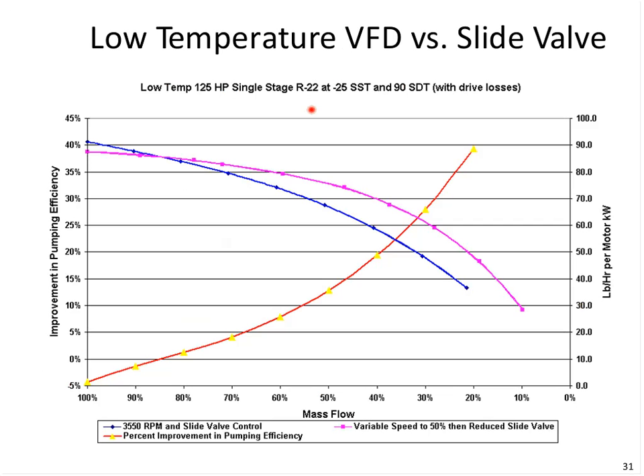Notice here's some data from a variable speed compressor and a slide valve. So notice at the bottom here we have a fixed speed with slide valve. That's portrayed by this curve. And over here we're looking at pounds of refrigerant per kilowatt, or quantity of refrigeration per kilowatt. So the higher the number here, the more compression we're getting per kilowatt. And then if we use that same compressor on variable speed, our efficiency gain is then portrayed by this curve on the bottom here that's showing improved efficiency of pumping the refrigerant with the compressor.